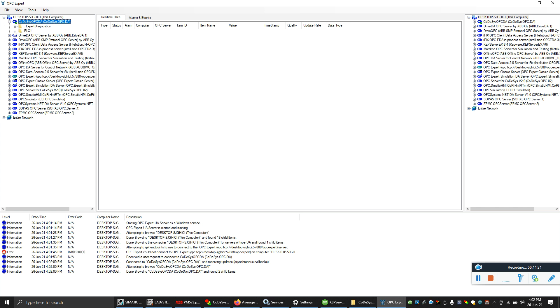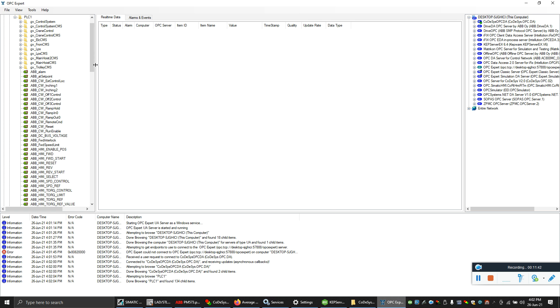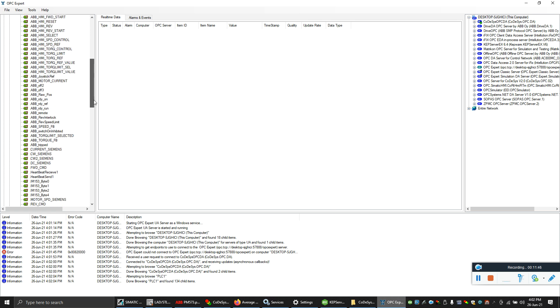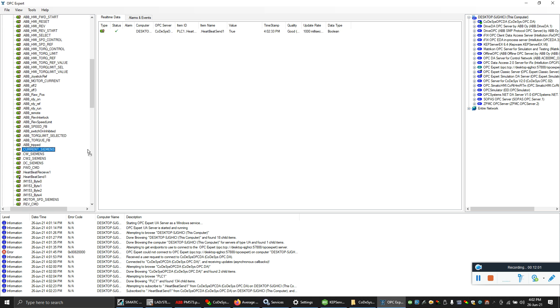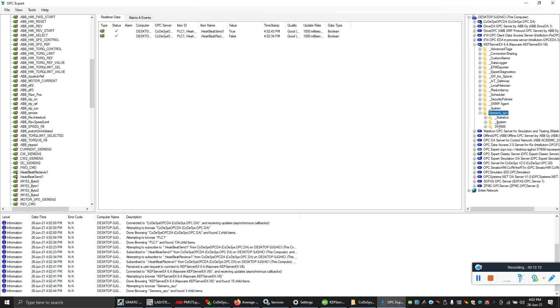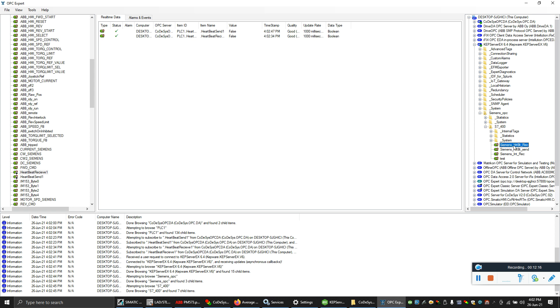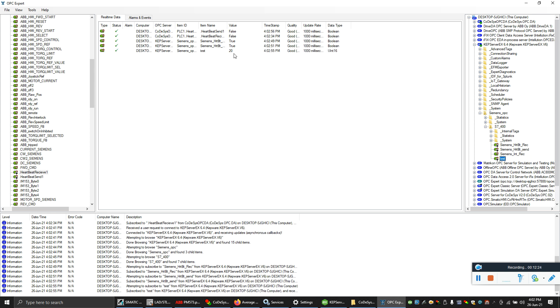It already detected my PLC and you can see all the variables we configured have appeared in the OPC server. Let's check if we are receiving the heartbeat value. The 'heartbeat send' tag is there — you can see it is toggling. Now let's also open the KEPServer for Siemens. You can see the channel, and the tags we created are all there. The test tag should show 20 — yes, it's showing 20. Configuration is confirmed correct.